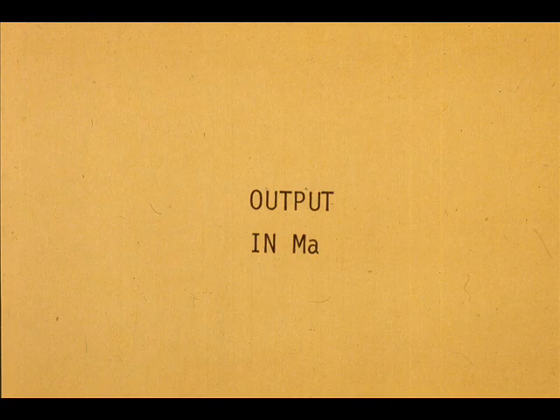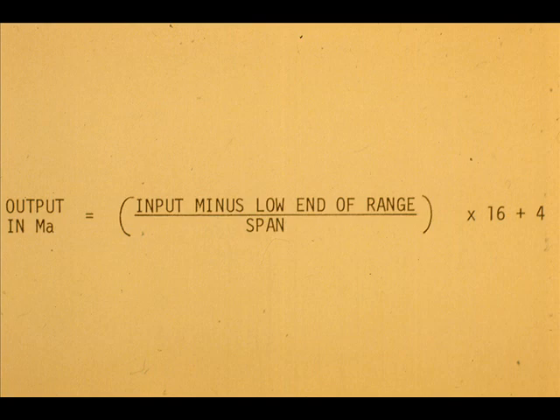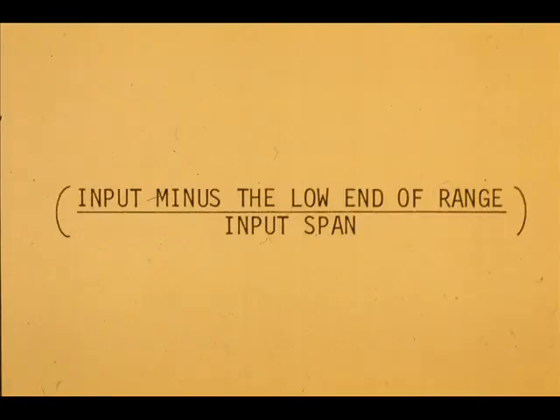For any 4 to 20 milliamp output transmitter having linear inputs, the output can be calculated from this formula. The output in milliamps equals the input minus the low end of the range, divided by the span, times 16, plus 4. This expression is simply the percent of total span represented by a given input.